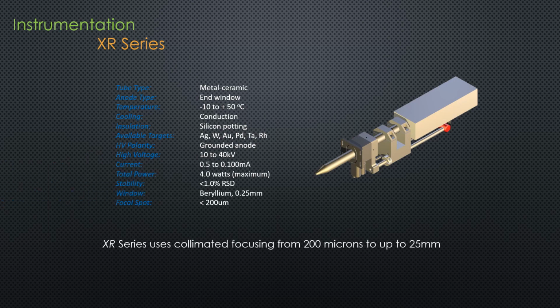The XR series runs at 10 to 40 kV. Collimators are screwed onto the end to vary the spot size and house the transmission filters. Spot sizes can be around 200 microns right at the sample surface up to 25 millimeters to make a very large bulk analysis.